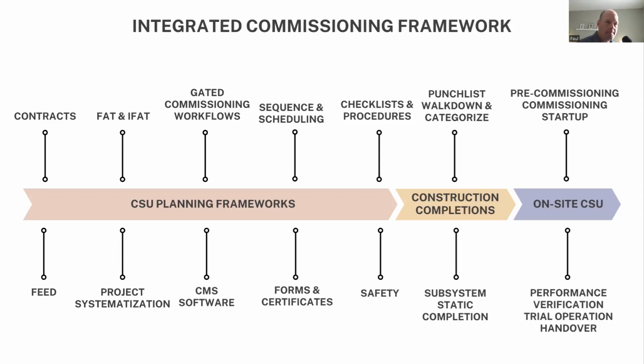So then our last framework here is really the on-site commissioning and startup process, and there are six frameworks involved. The ones you'd be familiar with are pre-commissioning activities, equipment level testing to get, say, your pump up and running, not necessarily interfaced with everything, but equipment checks during pre-commissioning. Once we've checked each individual piece of equipment, we move on to subsystem level testing, which is our commissioning, where we expect a lot of the equipment to work together as a subsystem or system, verifying integration to our control systems, that the pump, the motor, the power system, all of that equipment is functioning as one subsystem in the project to verify at a commissioning level.